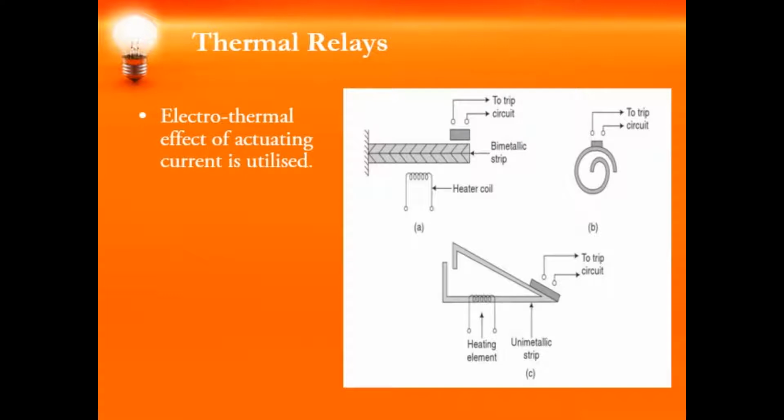This thermal element is basically a bimetallic strip. You can observe here, this is a bimetallic strip. Usually it is wound into a spiral to obtain a greater length, which results in a good sensitivity.